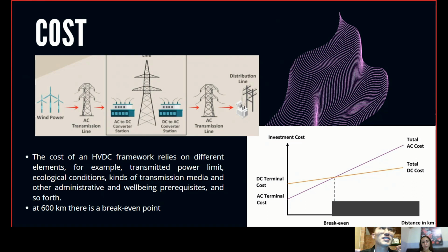As you can see, the cost of HVAC and HVDC transmission varies with respect to the transmission distance, showing in the graph the break-even point. The cost of the HVAC transmission line is cheaper than the HVDC, but after this equilibrium point, the HVAC cost increases. This is because it is necessary to correct an inefficiency of the transmission system generated by the reactive power that is only generated in alternating current. To compensate for this, capacitor banks and reactor banks are used approximately every 50 or 40 kilometers, rectifying the voltage, while in HVDC this does not occur because there is only active power producing the work.